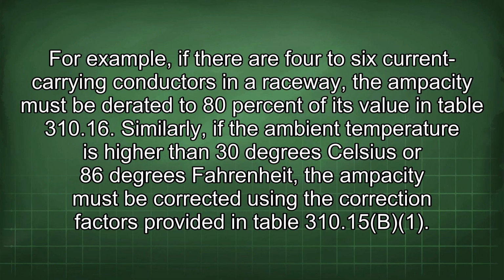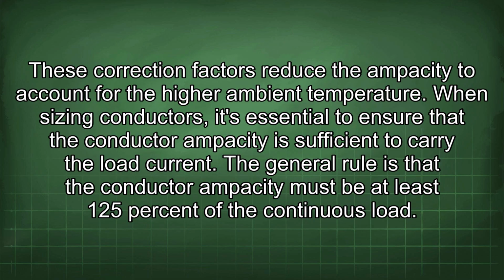Similarly, if the ambient temperature is higher than 30 degrees Celsius or 86 degrees Fahrenheit, the ampacity must be corrected using the correction factors provided in Table 310.15. These correction factors reduce the ampacity to account for the higher ambient temperature.